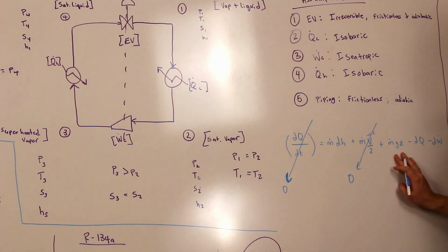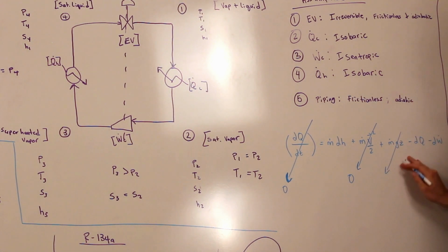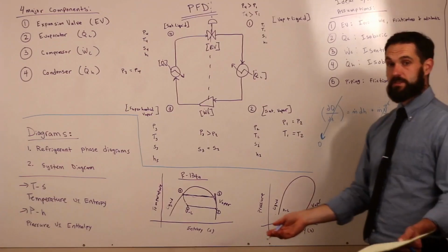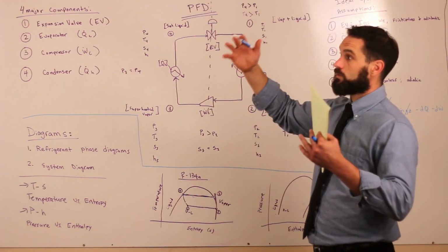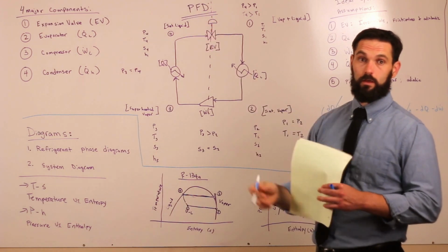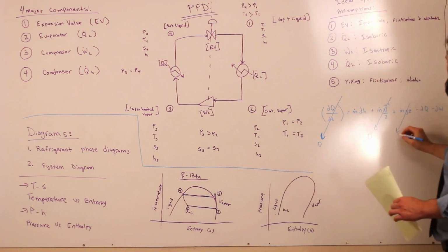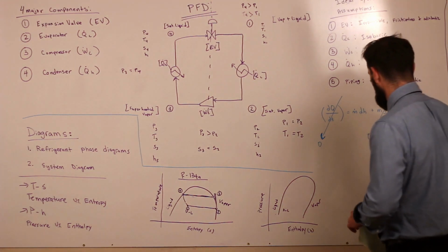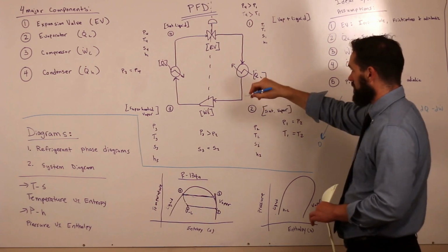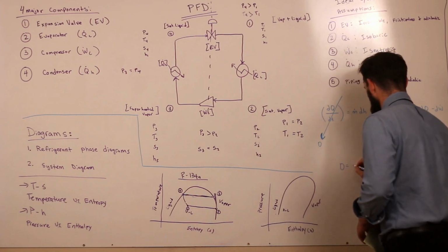We're also, at least not for our base case here, going to really consider the gravitational difference. But depending upon your system and your plant, if you have a refrigeration unit that goes very high up, maybe to an overhead condenser or something that's on a tall platform, this could potentially become not negligible anymore. So when we reduce down our equation, the equations that we're going to be using here to evaluate this will look something like this.